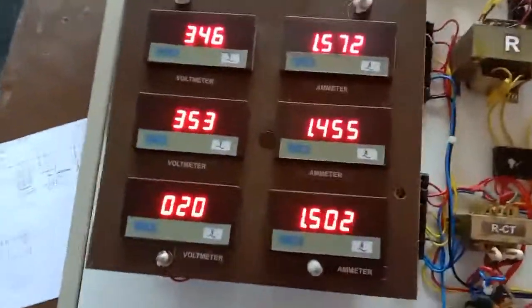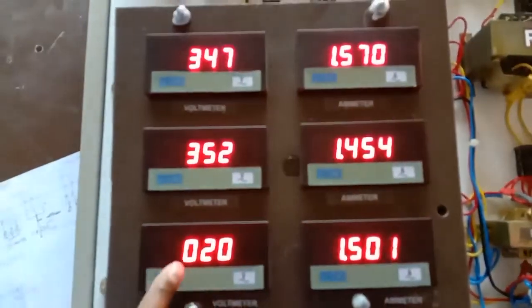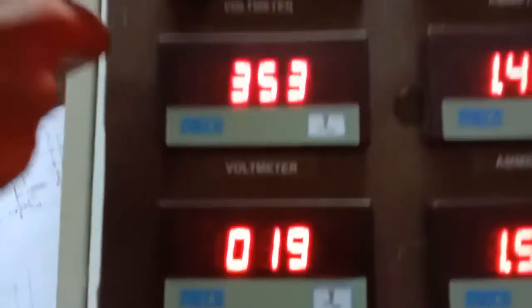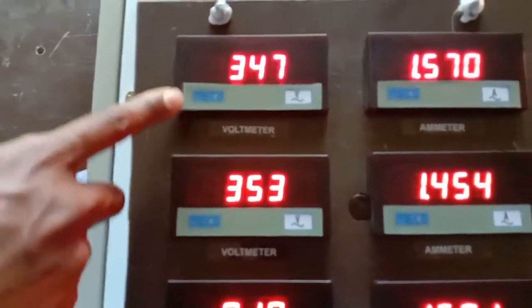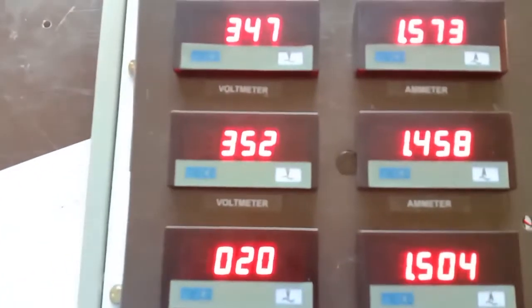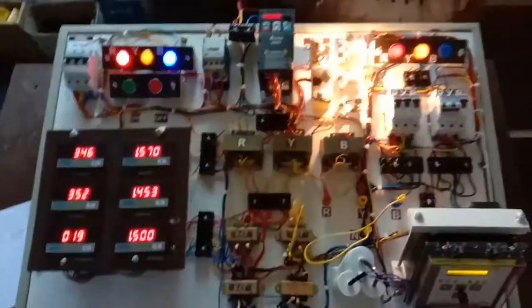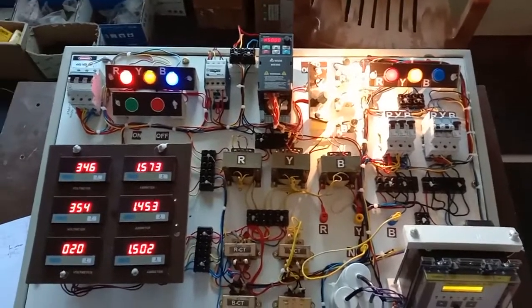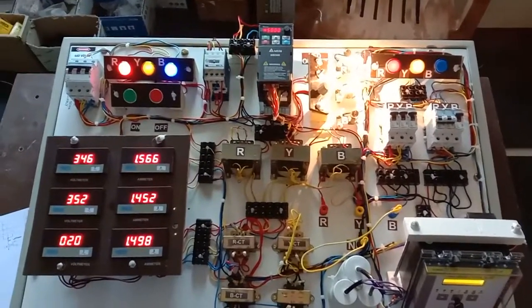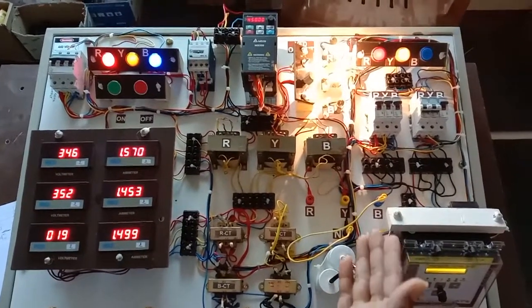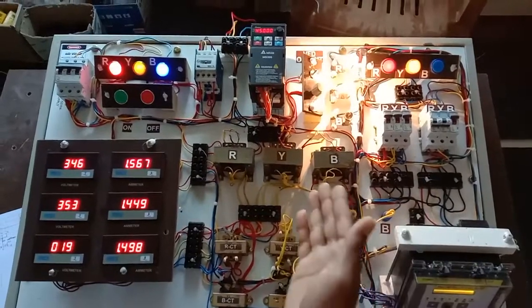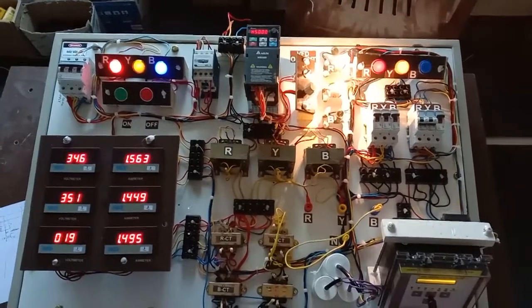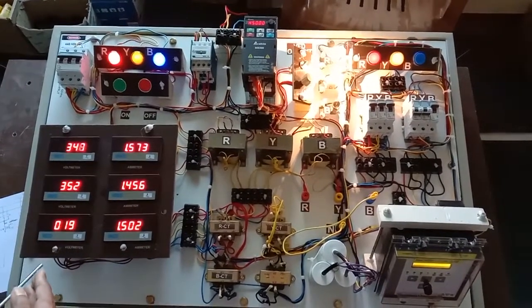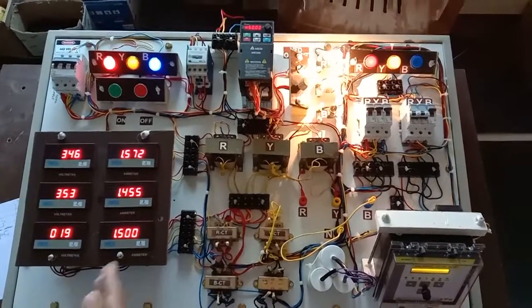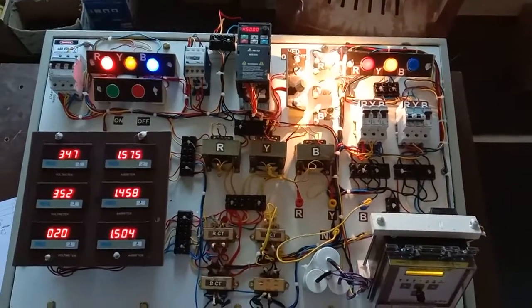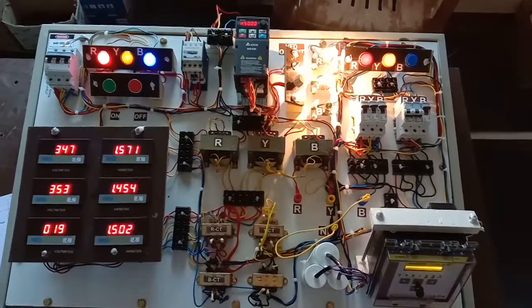Now you can observe the voltage in B phase has reduced, and the remaining two phases are increased by √3 times. This is one more important condition which we have to observe. So these are the different LG faults we have created on this ungrounded system. We can observe the fault creation and detection MCBs, LED positions, load lamps, relay indication, alarm and trip indications, and the voltmeter readings under fault condition, and this is the complete demonstration for the ground fault project for the ungrounded system.